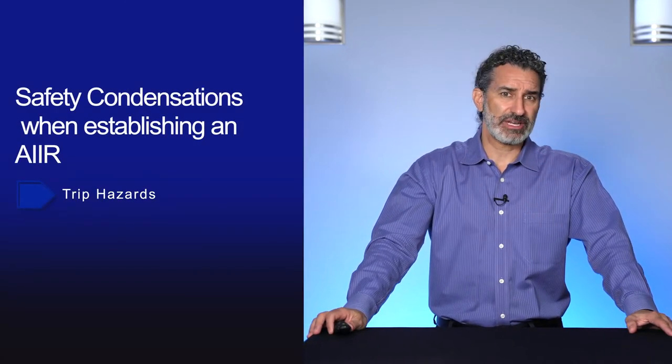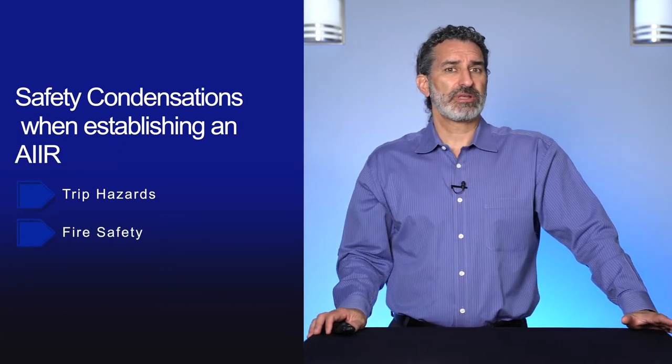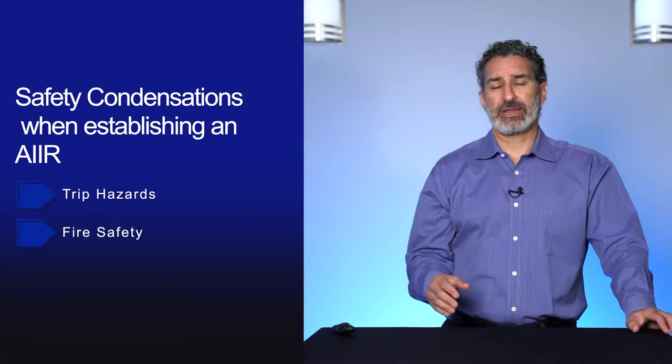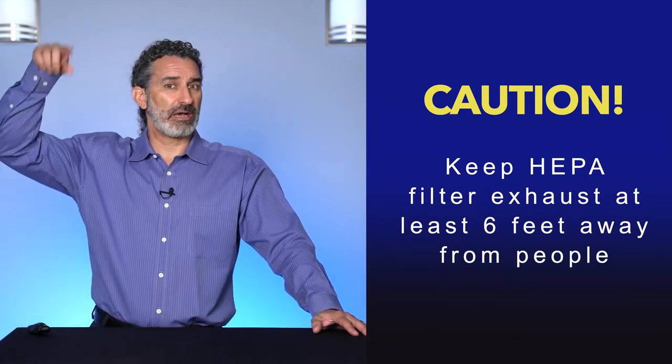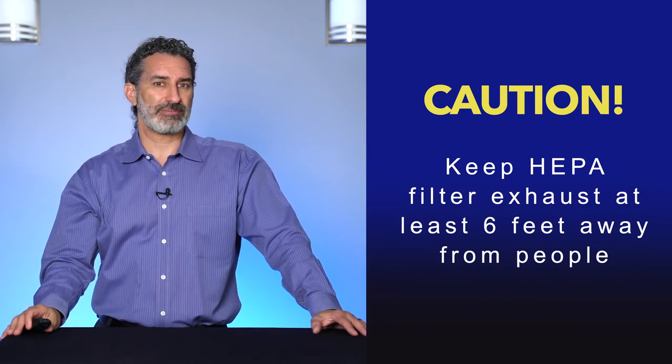There are many safety considerations when establishing an AIIR, including trip hazards and fire safety. HEPA-filtered exhaust, although it should have negligible infectious particles, should not outlet near people — in case of HEPA system failure. Keep HEPA-filtered exhaust at least six feet away from any people, and generally run ducting outside the building up to the roof so exhaust is released into the atmosphere and not near passersby, roads, sidewalks, paths of travel, or outdoor air inlets for your HVAC system.